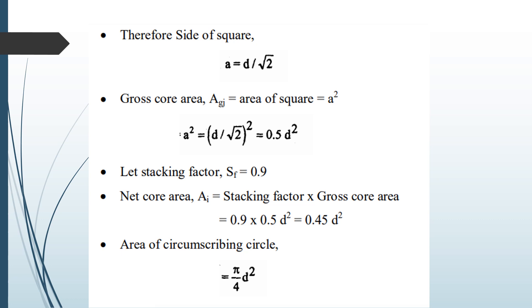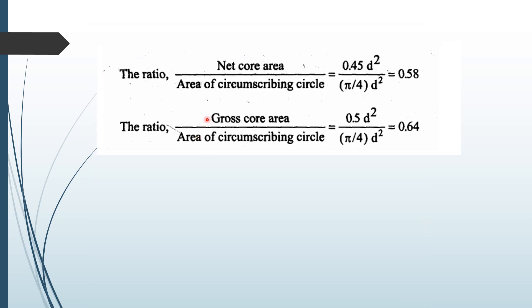Assuming a stacking factor of 0.9, the net core area ai = 0.9 × 0.5 d² = 0.45 d². Using the area formula for a circle, the area of the circumscribing circle = π/4 · d². With these calculations, we can obtain the ratio: net core area divided by area of circumscribing circle = 0.45 d² / (π/4 · d²).